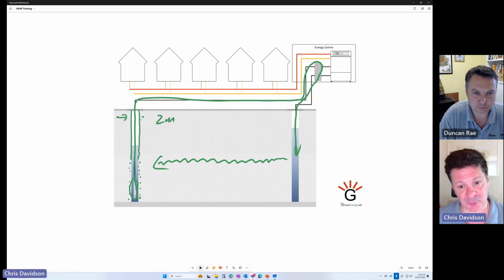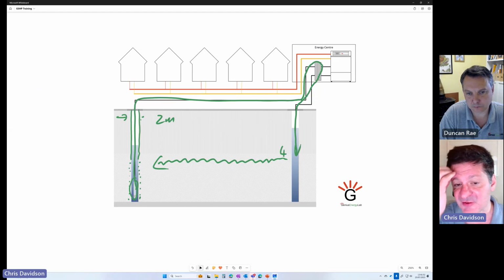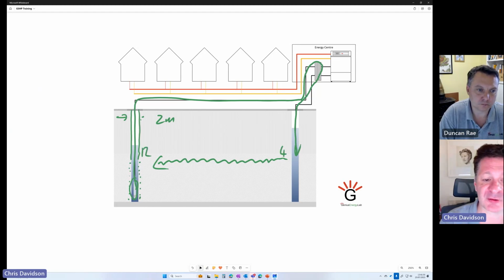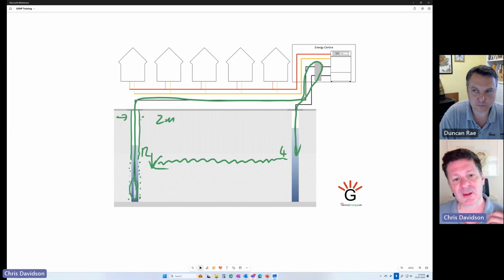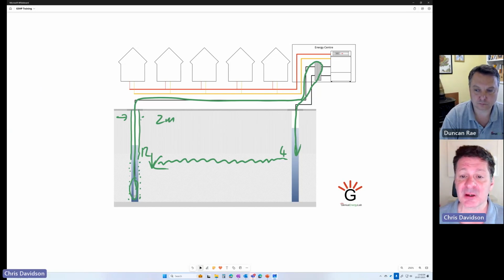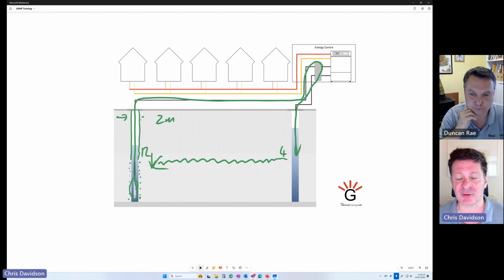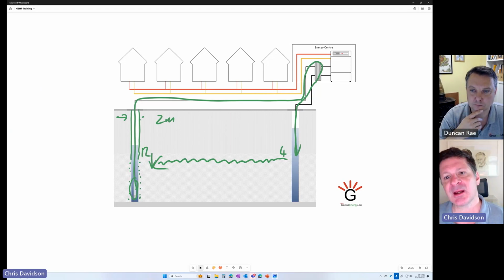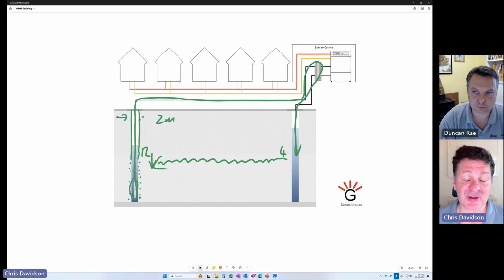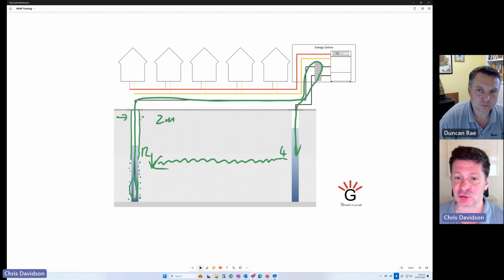Now, a couple of things to point out on these. You do want to make sure that you've got adequate spacing between your abstraction and your recharge wells to make sure you're not getting any short cycling on these systems. So we might be putting water into the ground as low as, say, 4 degrees C, and we don't want to see this water, which is perhaps starting at 12 degrees C, start to drop in temperature as a result of what we're doing at the recharge well. Second point to make is there are statutory licensing requirements in the UK for these types of systems. The regulations are different in England, Wales, Scotland and Northern Ireland, but in the main, any size of system is going to require statutory licensing, and that licensing process can take over a year. So that's a significant issue when you're talking about construction projects.